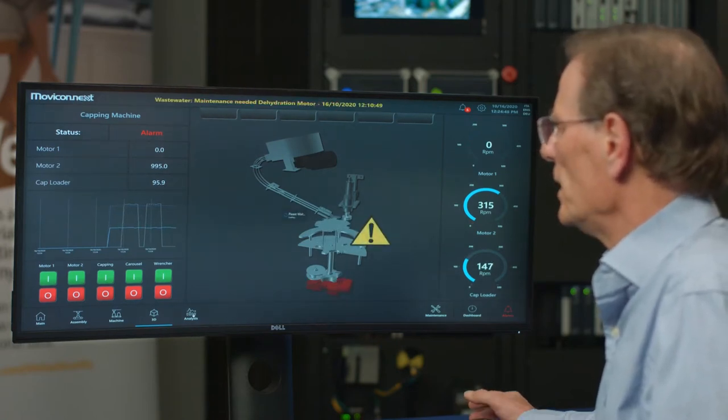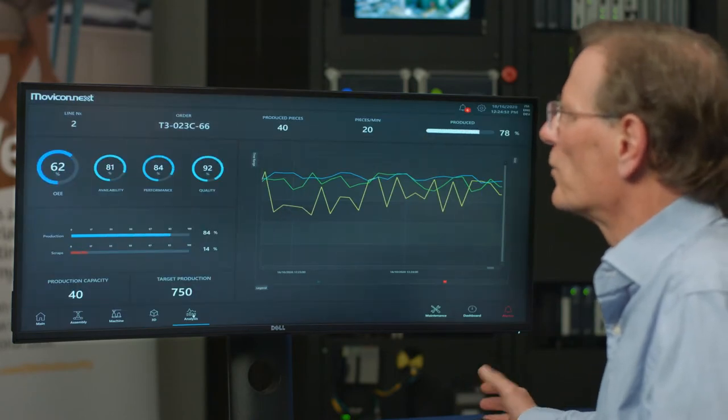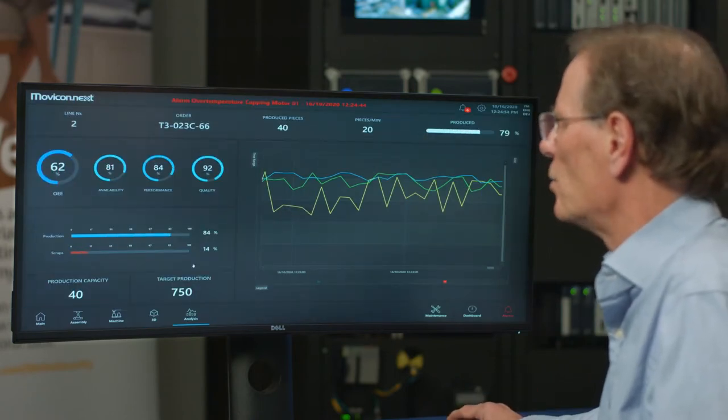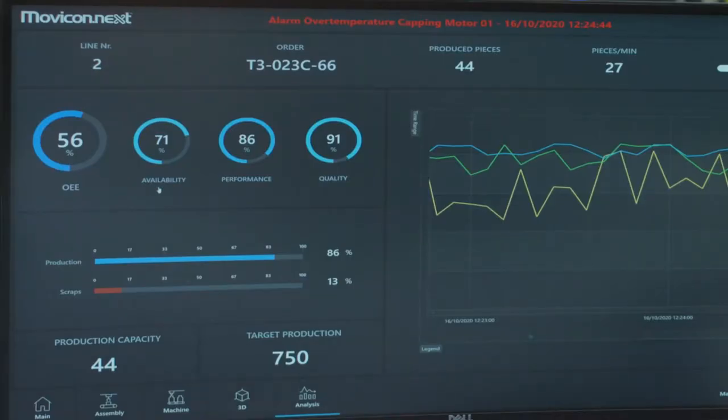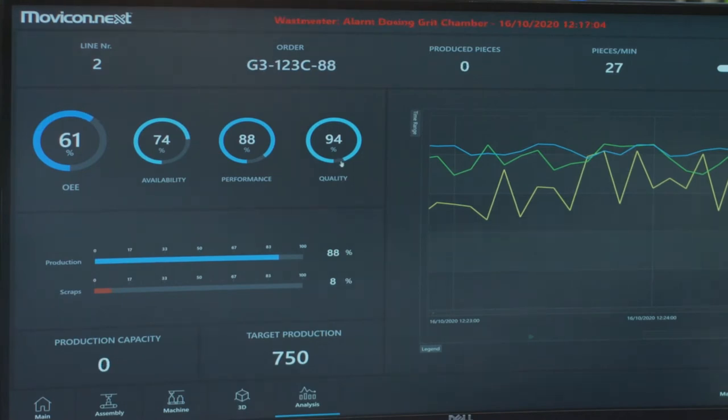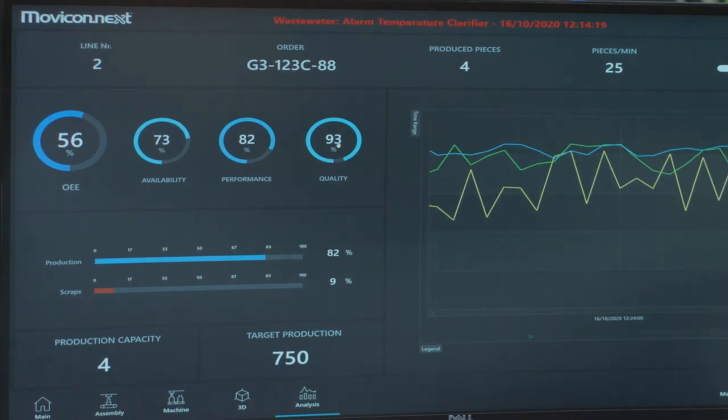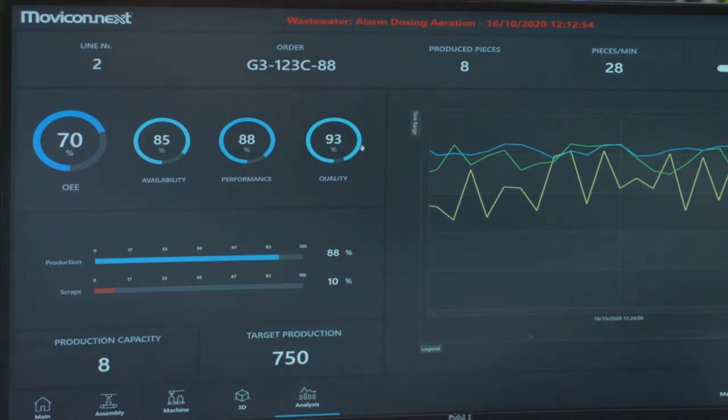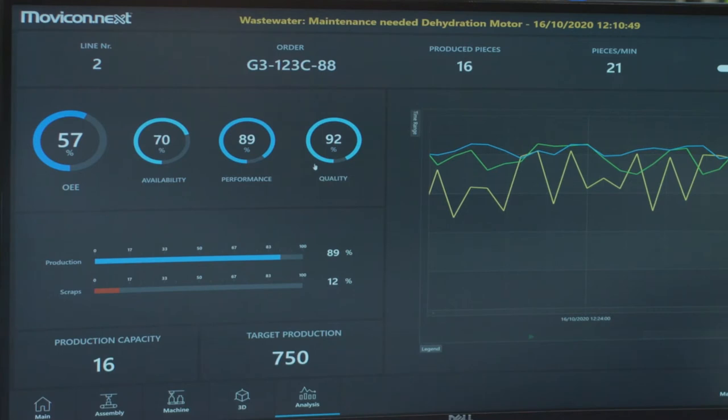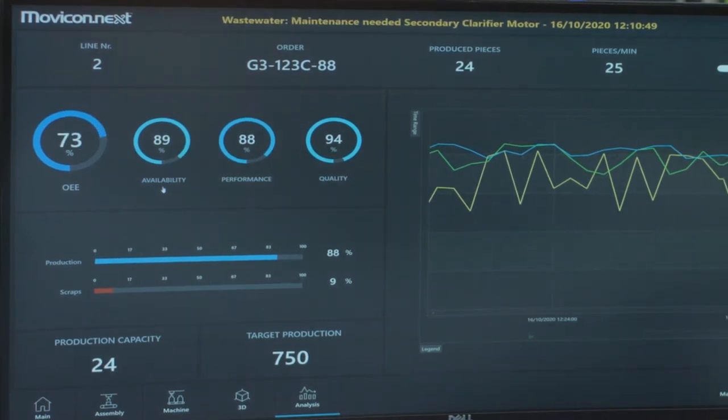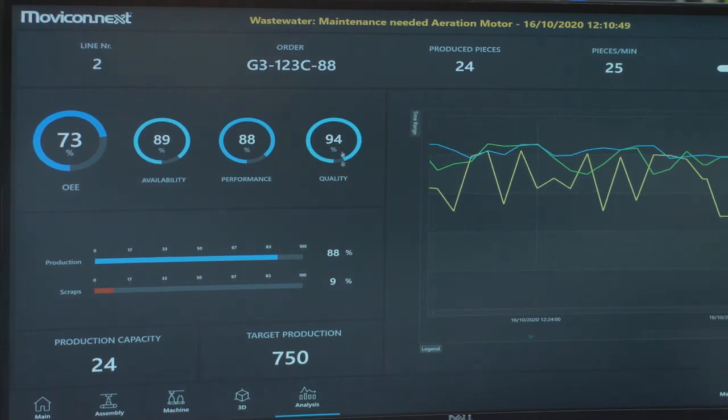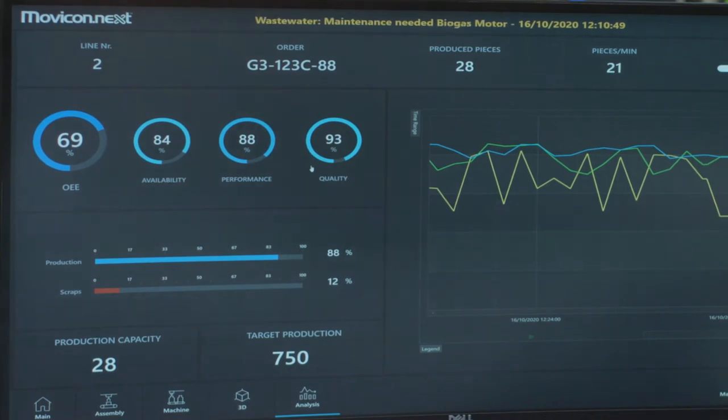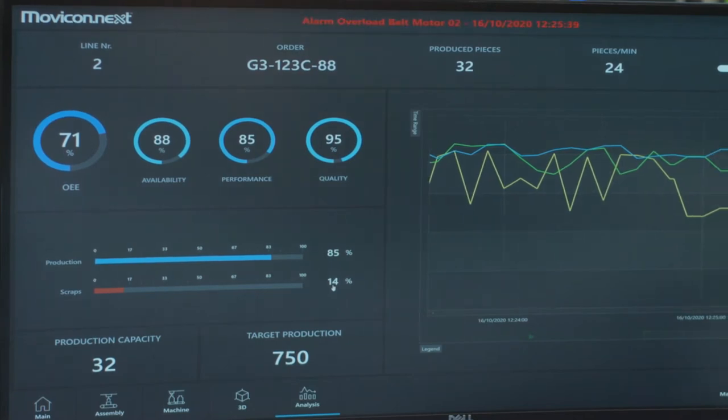From an analysis standpoint, here we have a capability called Overall Equipment Effectiveness, OEE. And here you're talking about what is the availability of your equipment for production, what is its current performance, and what kind of quality am I seeing? Am I producing the right product at the right time in the volumes that I expect? Am I scrapping portions of the product or is it all coming out well? This might even include the labels on the bottles. Are they skewed, in which case you have to maybe do some repair on it. So a lot of information is available through OEE. And a really nice thing about the Movicon Next product is you can get OEE very simply just built on top of the same product. You don't need a more sophisticated MES system, which can cost a lot of money and take a lot of time to get that basic capability around OEE. You can get it at the machine level, the line level, maybe multiple machines, and see where your problem area is and target those for improvements.